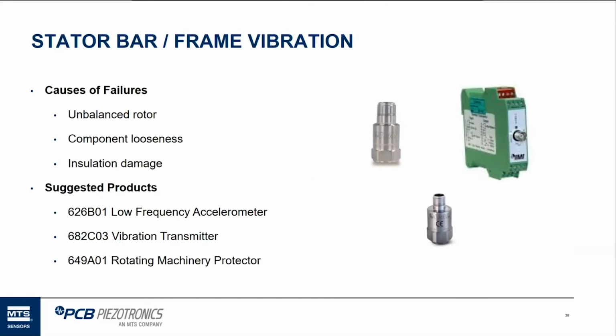It's used in a lot of different applications like reciprocating compressors or pumps. I've seen it used for looking at cavitation in the past. Also, a low frequency accelerometer and 4 to 20 output vibration transmitters are capable of providing output for stator bar frame vibration problems.